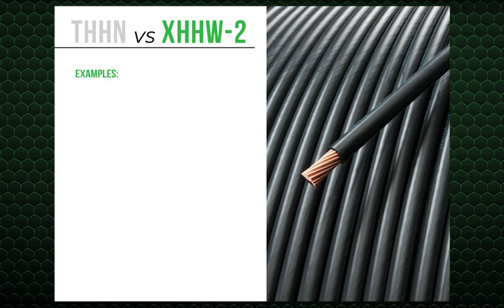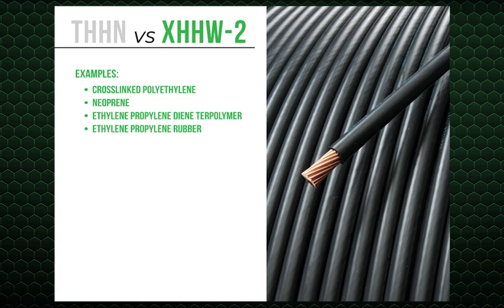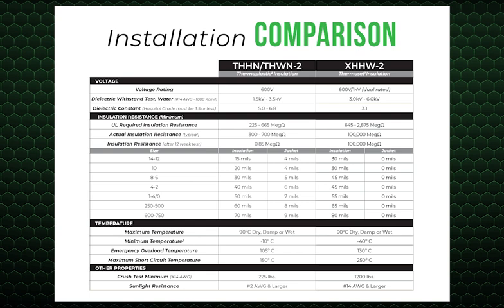Some examples of thermoset compounds are cross-link polyethylene, XLP or XLPE, neoprene, ethylene propylene diene terpolymer, EPDM, ethylene propylene rubber, EPR, chlorinated polyethylene, CPE, cross-linked polyolefin. Unlike THHN, XHHW-2 is dual-rated for 600 volt and 1 kV applications. UL dual-rated products must use a recognized 1 kV rated conductor and pass a higher voltage AC high pot test on the completed cable. Service wire's XHHW-2 XLPE insulation can withstand voltage spikes that would cause damage to THHN.